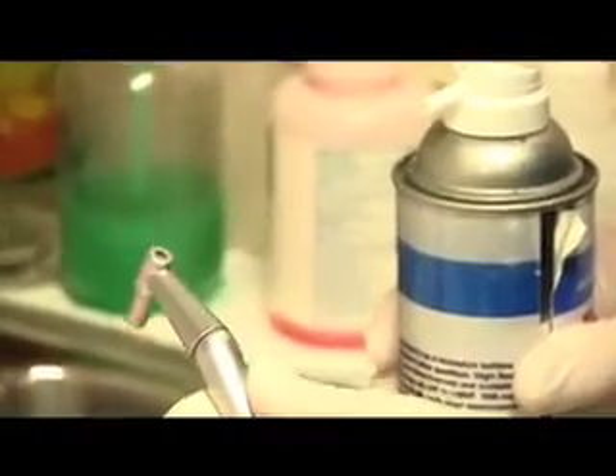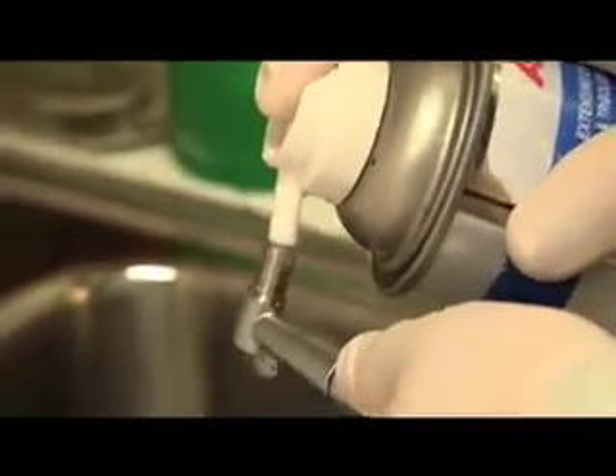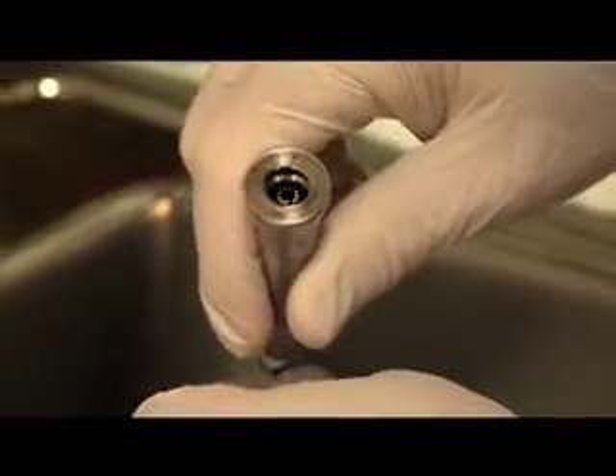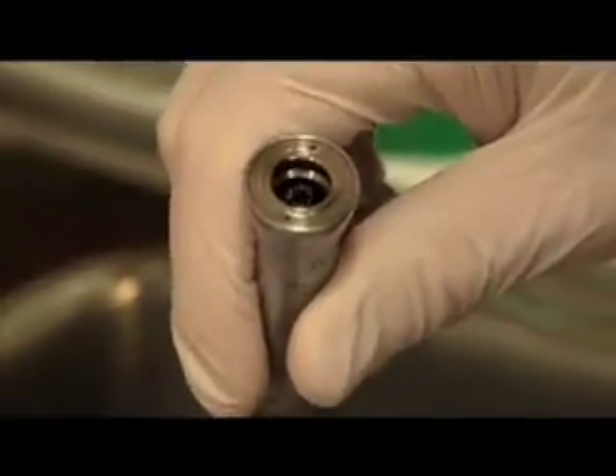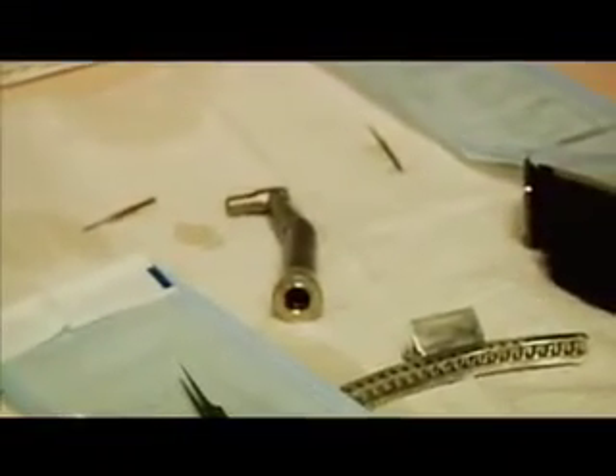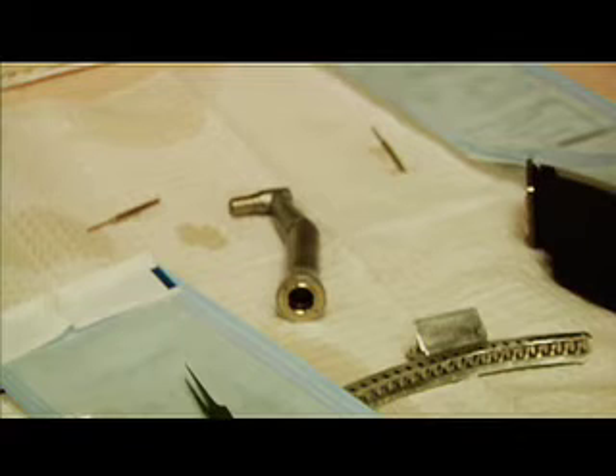After soaking and sterilizing the harvester handpiece, you should thoroughly lubricate the barrel from the top and bottom. Be sure to get plenty of lubricant inside it. Then, just to be sure, we recommend working the lubricant into the gears by taking a punch, inserting it into the head, and rotating the punch by hand to make sure the lubricant is worked into the gears. When done, wipe the excess lubricant from the outside of the handpiece with a paper towel. Be sure not to autoclave the contra-angle harvester handpiece. This can ruin the rubber O-rings within.